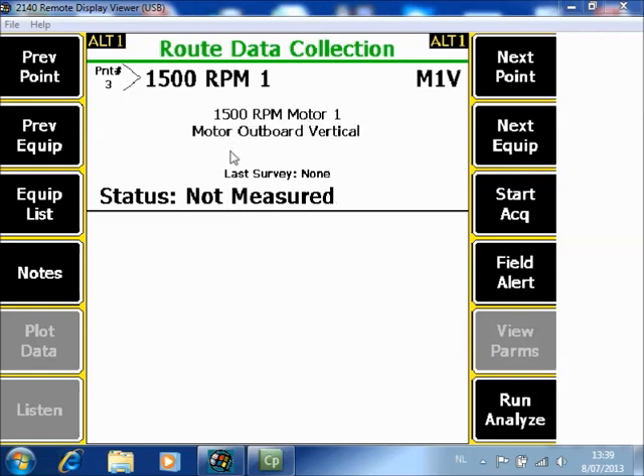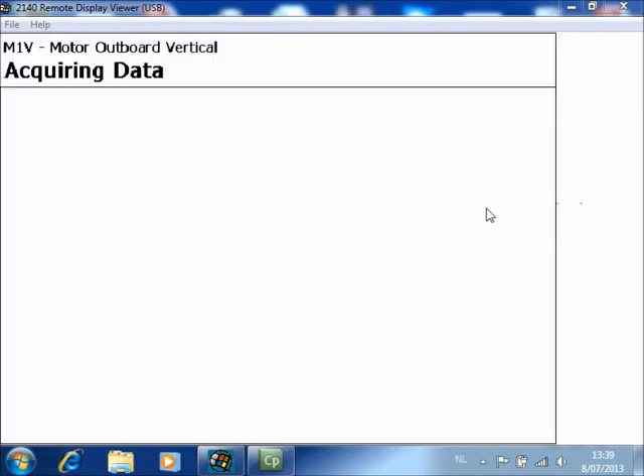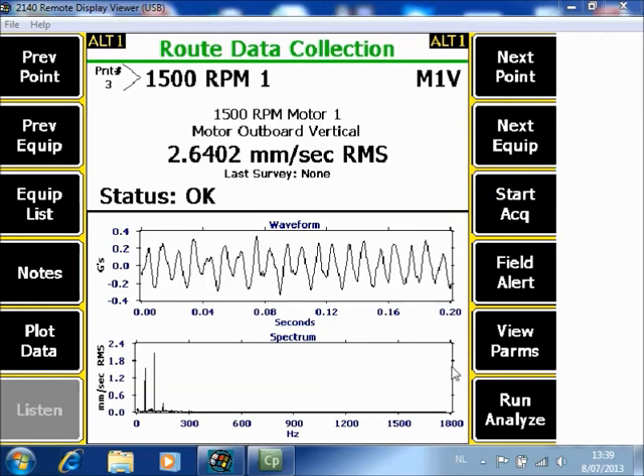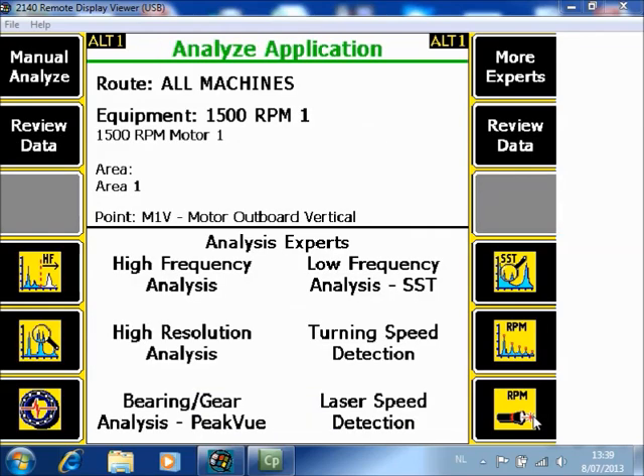Let's first take regular route data. I start the route data acquisition by pushing F9 start acquisition. A spectrum is measured roughly up to 1800 Hz. If you now go to Run Analyze F12 and select F4 High Frequency Analysis.